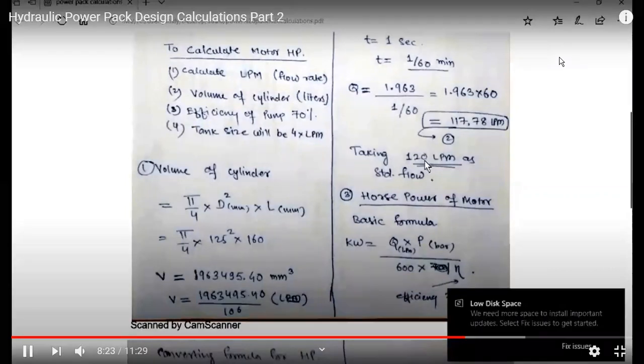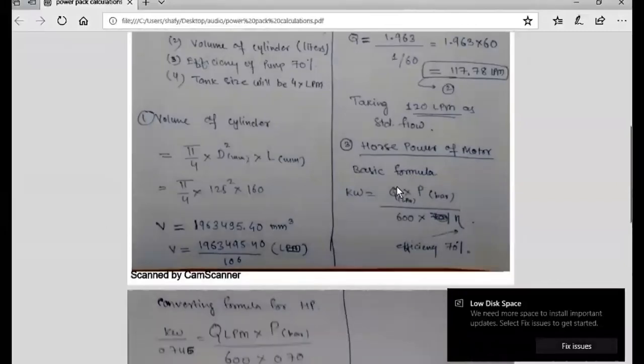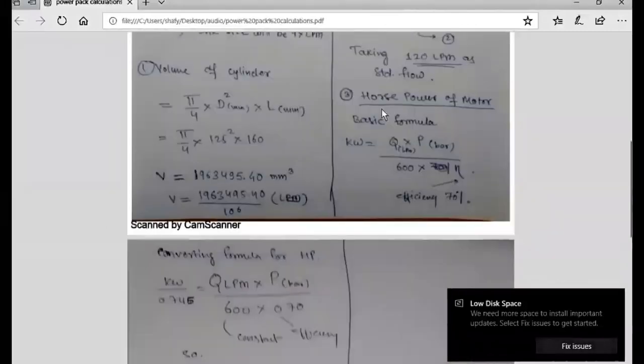Then we calculate the horsepower. Formula for horsepower in kilowatts is Q, that is liters per minute, and P is your pressure in bars. Q is the discharge in liters per minute and P is pressure in bars, divided by 600 into efficiency. Efficiency will be dependent on pump and specification as per the manufacturer's catalog.